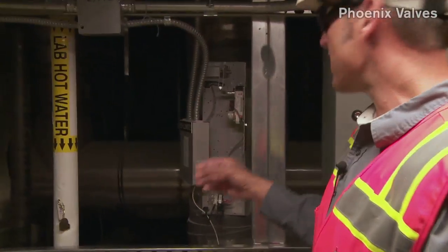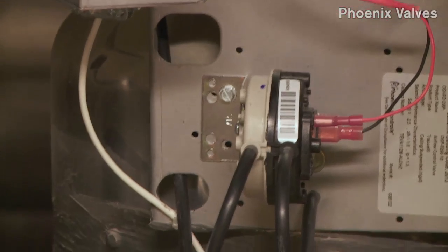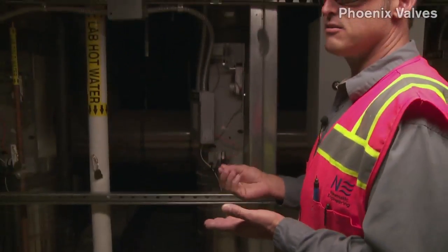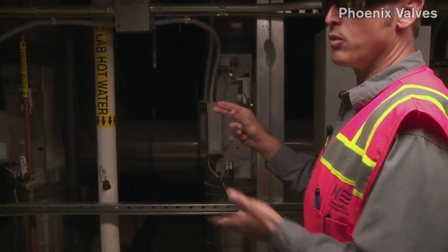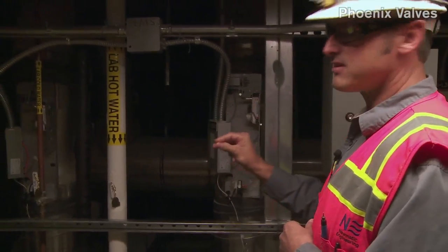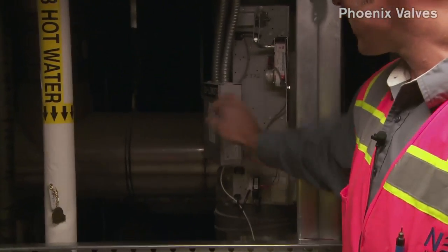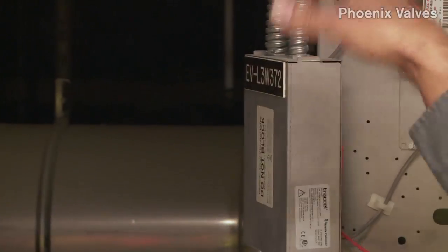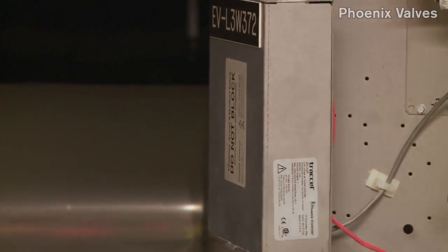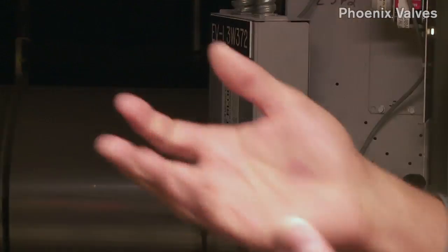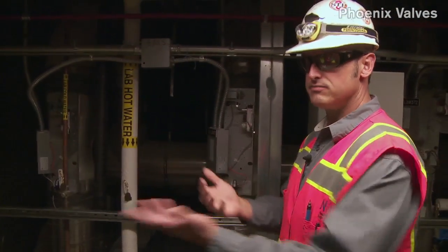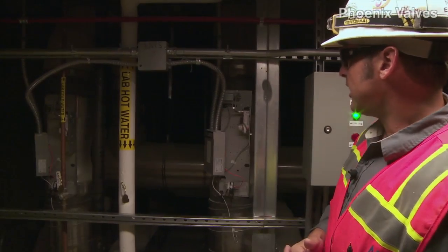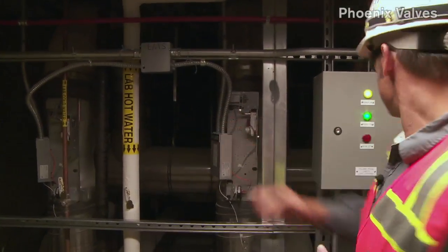If the fans drop off, there's a little dry contact switch in here. As long as the exhaust or supply air is within the specifications it needs to be, it holds that switch open. When the fans shut down, it closes and it sends a signal through these wires into our board, which in this building is tied directly to the Johnson Controls front end, so they should see an alarm pop up there, probably going to you guys. This is just a regular general exhaust valve.